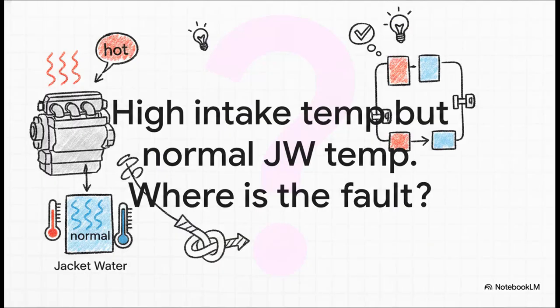Let's run a quick scenario. Imagine you're out on a service call. The ECM is throwing a code for high intake manifold temperature. So, you check the jacket water block outlet temperature and find it's completely normal. What's your next move? Where is the actual fault?